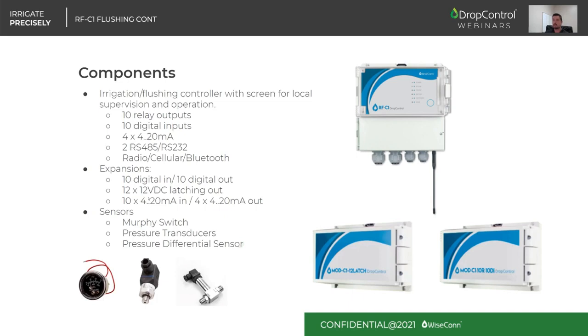And for the flushing in particular, we are capable of controlling those cycles with multiple types of sensors. We can use the regular pressure differential switch, which a lot of people will use, the Murphy switch. You can use a pressure transducer, which is basically having a pressure reading before the filter and one after the filter, and the controller will calculate the pressure differential that we are going to use to trigger a flushing cycle. Or you can have a pressure differential transducer that is going to immediately give you that difference.